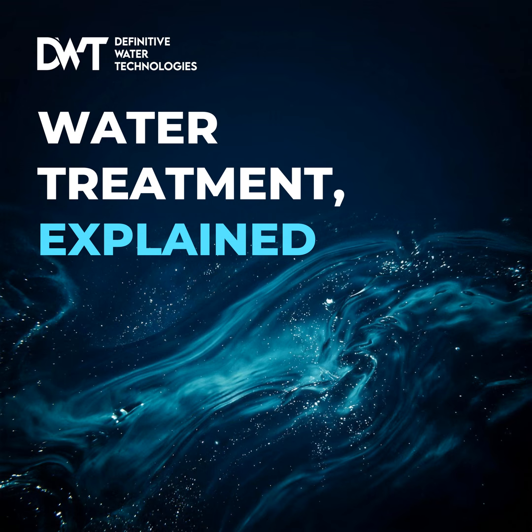It really is. We're basically talking about a teardrop every few seconds, which brings up a massive issue on the plant floor. The standard pump sizes. Yeah. The smallest standard industrial pumps are usually around 5 liters per hour. If we need 0.06 on a 5-liter pump, that's 1.2% of its maximum capacity. Which completely shatters the 20 to 80% rule.